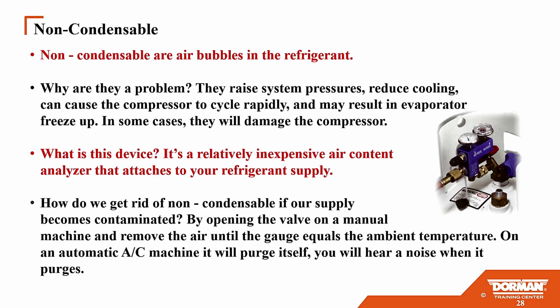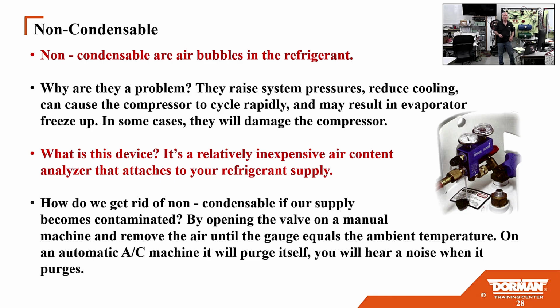Non-condensable air, that is a huge issue. It raises the temperature and system pressures, and reduces cooling. So here's a device, relatively inexpensive, that attaches to your refrigerant supply to see how much non-condensable air you've got.